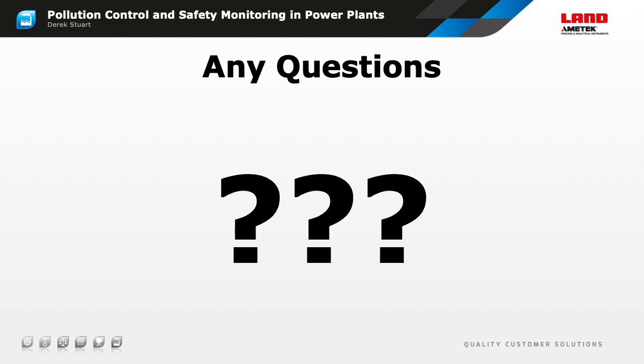In my experience with CO monitors across a number of sites, a number of users, a good starting point for a CO alarm is somewhere between 100 and 200 parts per million. That's well above any level where the instrument drift is going to give you a nuisance alarm. In most, but not all cases, that's high enough that it will not give you a nuisance alarm because of normal process fluctuations, but there are exceptions to that. But it's certainly low enough that you will still get a rapid indication and a rapid alarm taking place when the process does begin to get into a bad state and where you do begin to see spontaneous combustion going on.